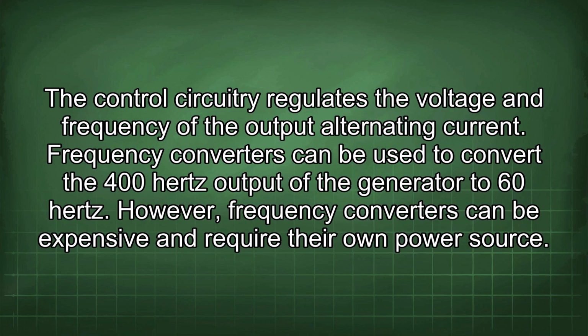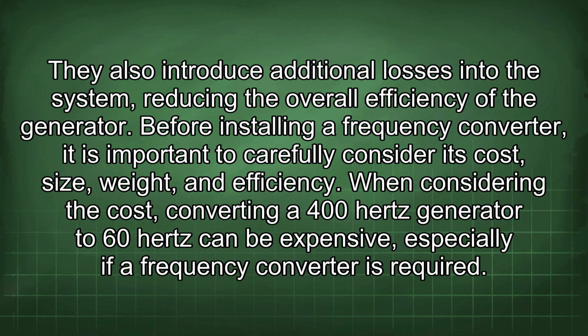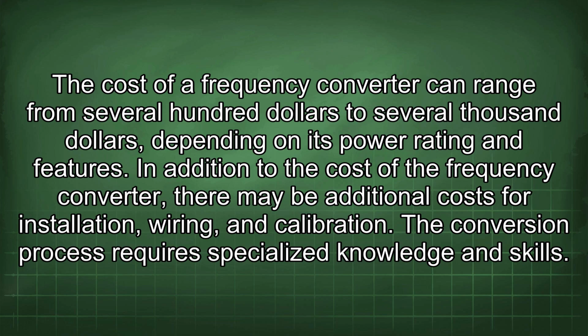However, frequency converters can be expensive and require their own power source. They also introduce additional losses into the system, reducing the overall efficiency of the generator. Before installing a frequency converter, it is important to carefully consider its cost, size, weight, and efficiency. When considering the cost, converting a 400 Hz generator to 60 Hz can be expensive, especially if a frequency converter is required. The cost of a frequency converter can range from several $100s to several $1,000s, depending on its power rating and features. In addition to the cost of the frequency converter, there may be additional costs for installation, wiring, and calibration. The conversion process requires specialized knowledge and skills.